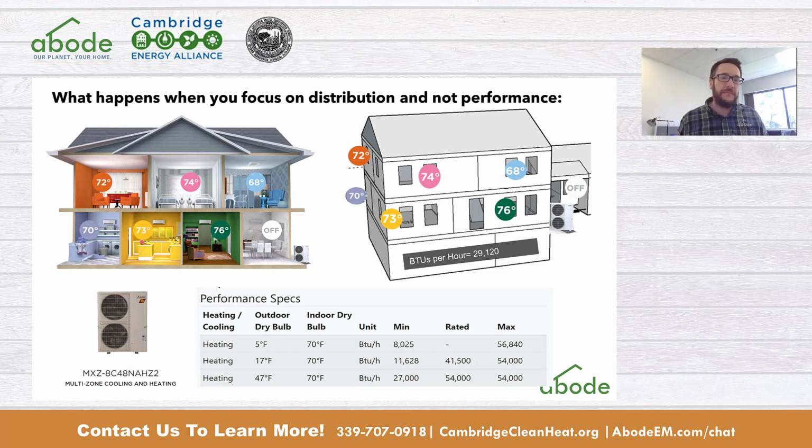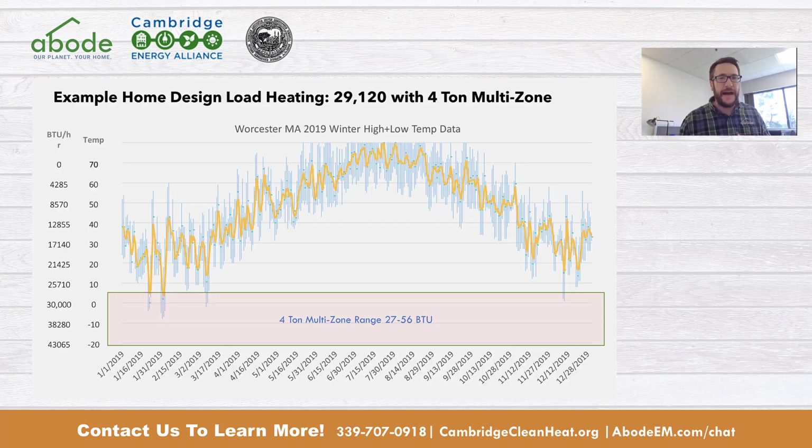And this is the marketing material, and this is what a lot of ductless installers talk about. We'll put one in each and every bedroom, one in the living room, one in the kitchen. Say you have a house that needs 30,000 BTUs, and you need 7 indoor units. The only piece of equipment on the market right now that can take 7 pieces of indoor equipment is a 4-ton system. And this is what ends up happening.